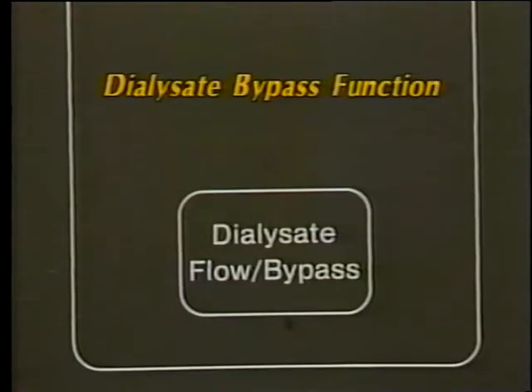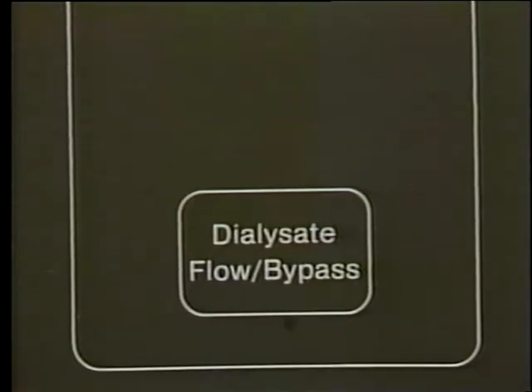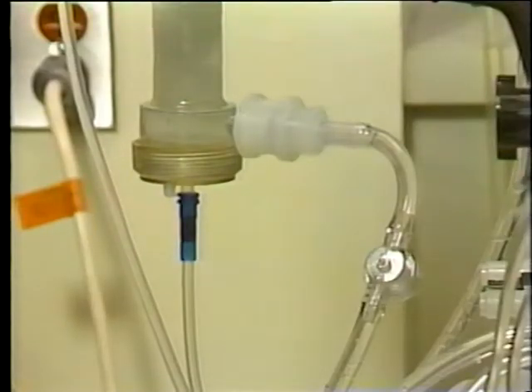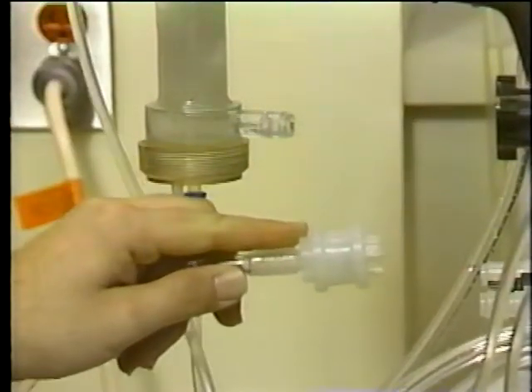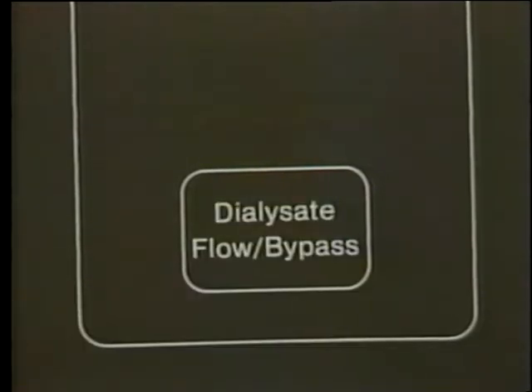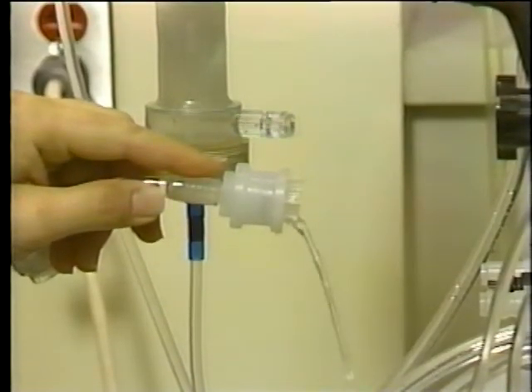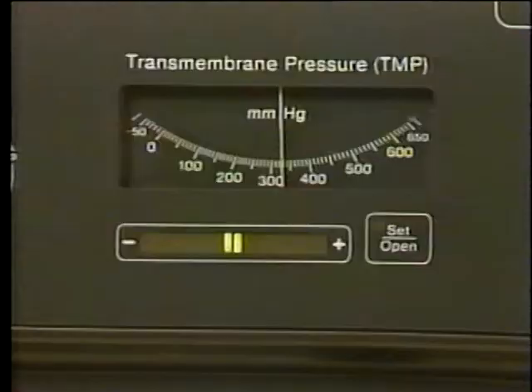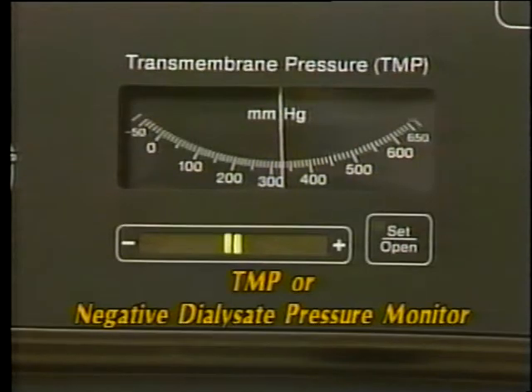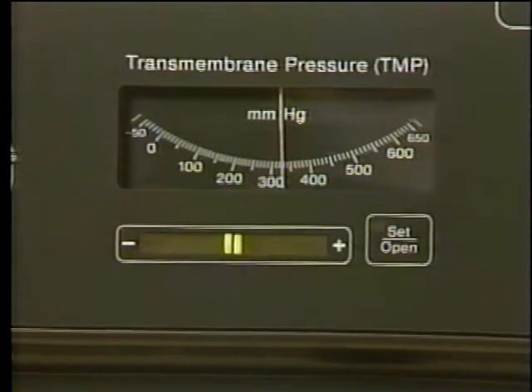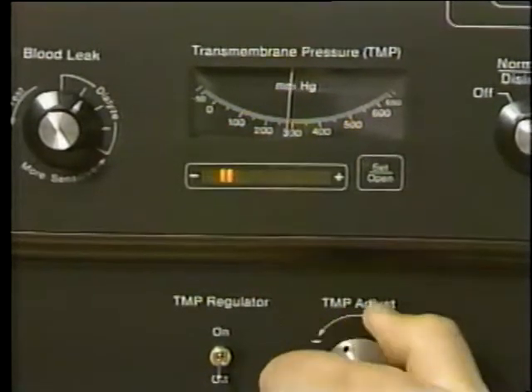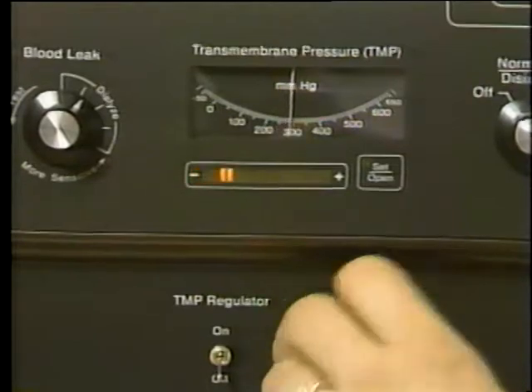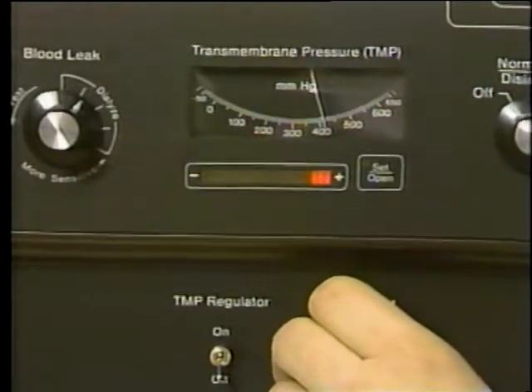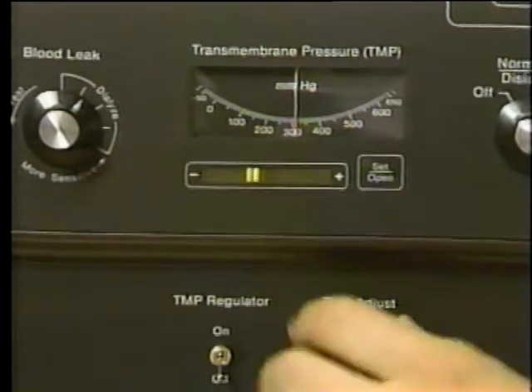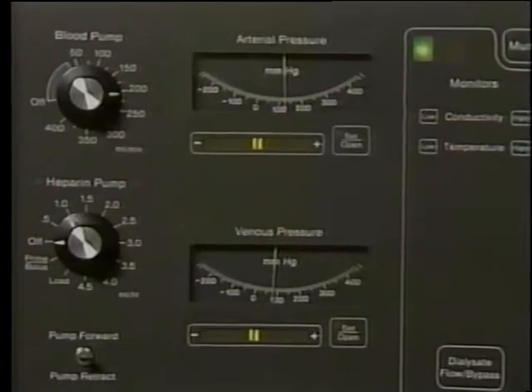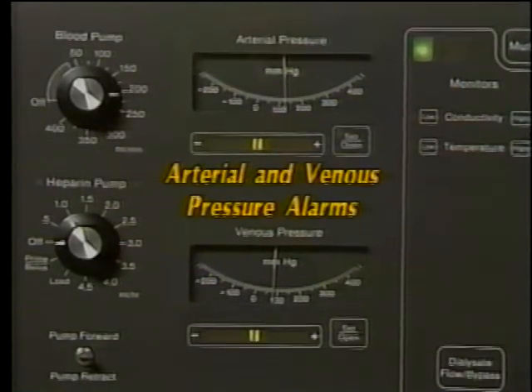The dialysate bypass function is a very important safety feature on the machine. The dialysate flow should bypass the dialyzer and go directly to the drain to protect the patient from overheated dialysate or an unsafe dialysate mixture. To test for bypass, make sure that the flow actually bypasses the dialyzer. The limits on the transmembrane pressure or negative dialysate pressure monitor must be set on those machines that require a manual setting once the TMP has been calculated and set. To test the TMP or negative dialysate pressure alarm, set your limits, violate them, and then verify both an audible and visual alarm.